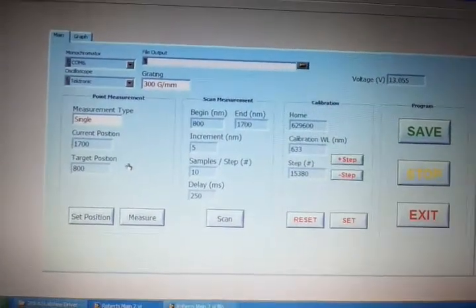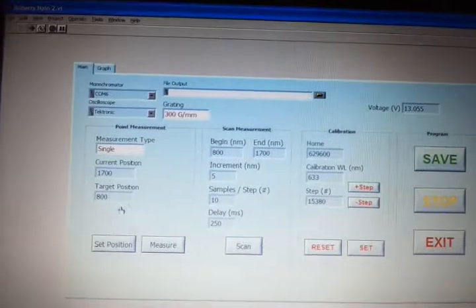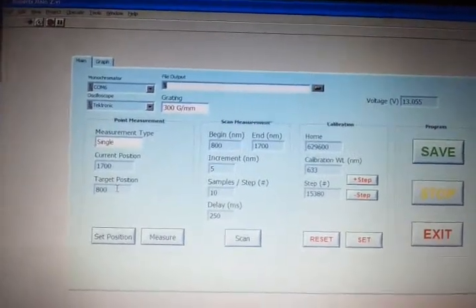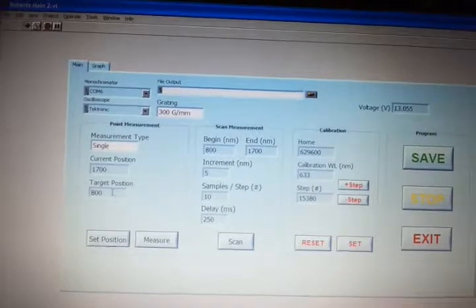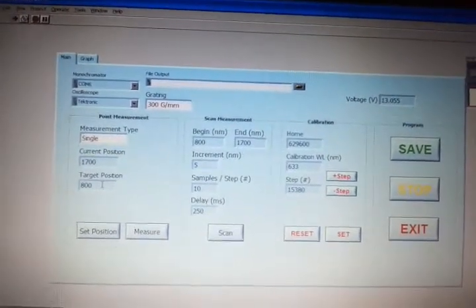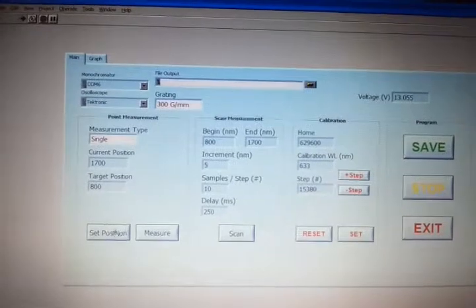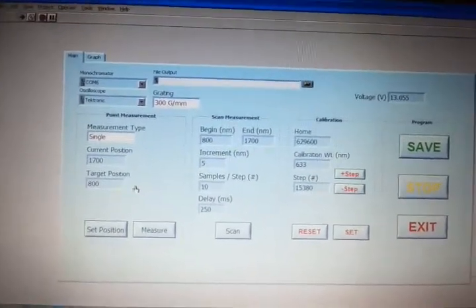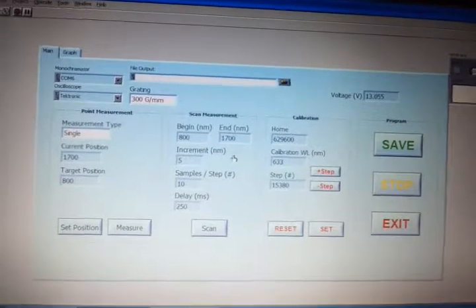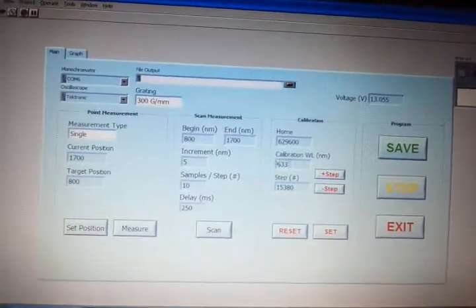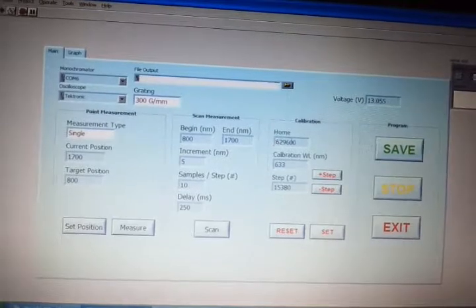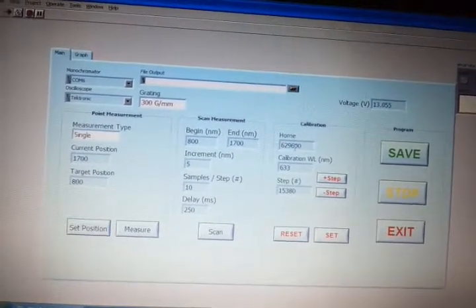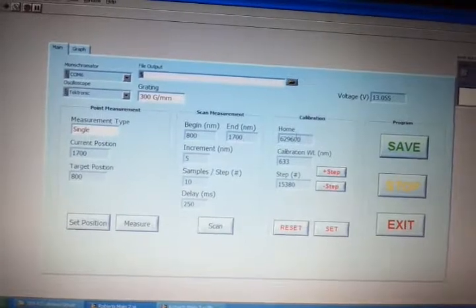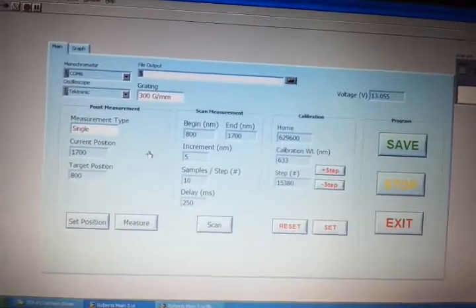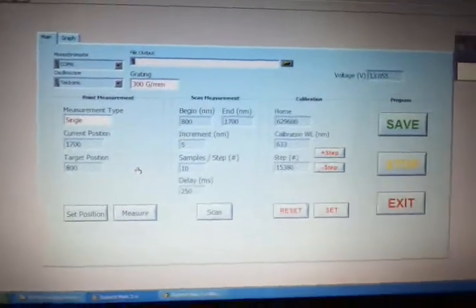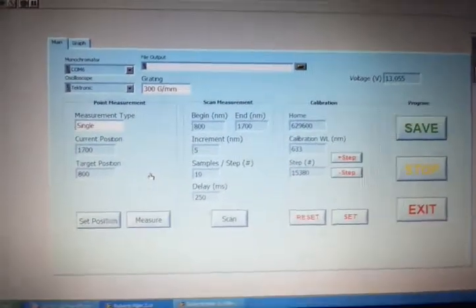If you want to see a single wavelength, you can then go over here to target position, enter in the equivalent wavelength that you'd like to take a look at, and then say set position. That will make the monochromator go to that wavelength based on the calibration wavelength and the difference in the number of steps, or these counts. It's a simple linear transformation. It does not take into account any dispersive effects of the grating.